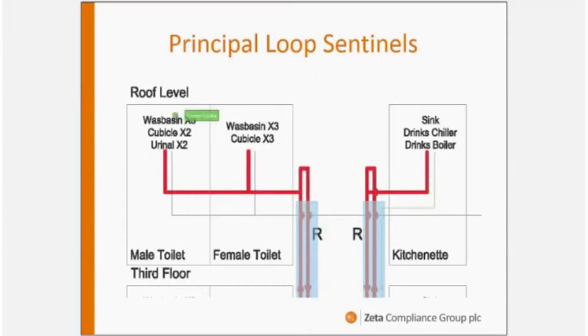So you can go to this tap here and run this and suck water up the flow leg to the tap and pass muster. But if there's a valve closed in that circuit, you could suck water up the return leg to there, or if it's simply not flowing up and over, you could draw water up there and still pass. Because it's not flowing, that downward leg there is cool or cold or warm or worse, and that could be a very, very substantial dead leg.